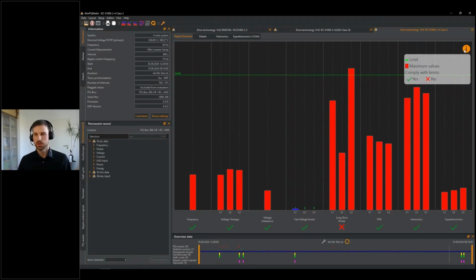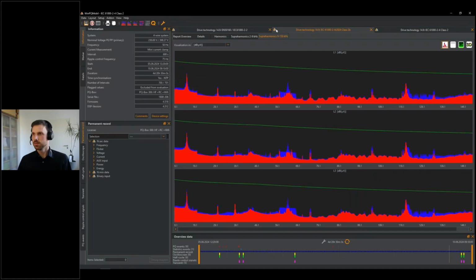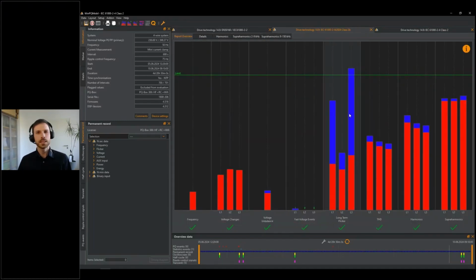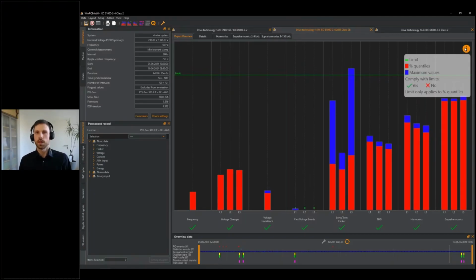So this information tab gives me a legend, and I see, okay, long-term flicker does not comply with the limit values. Well, if you remember, this is, for example, one detail that has to do with the 95% quantiles. The previous edition 2 did not compare anything against quantiles. The new edition does. So if you got only a few measuring points that are above the limit values, the old version considered it a no-go. The new version, I go to the overview, deals with a 95% quantile, and so it's not a problem. There's no red cross over here, and these values now comply with the limit values.